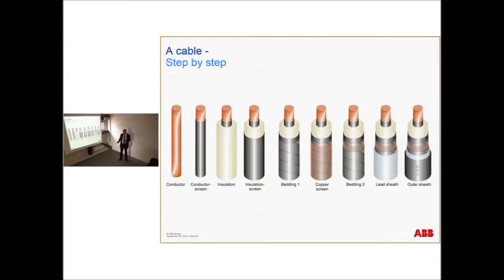You start with a conductor. You have a conductor screen, which is semi-conducting. Then you put on the insulation. Then you have a semi-conducting screen again. Then you have some kind of bedding before you put on the copper screen, if it's a land cable. Then you have another bedding, then you have the lead sheath, and then the outer sheath, and then you continue with armoring, if it's a submarine cable.